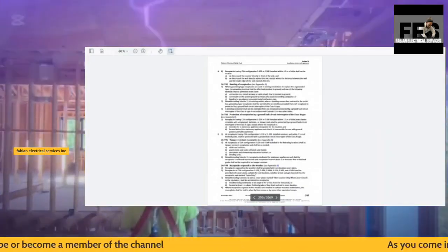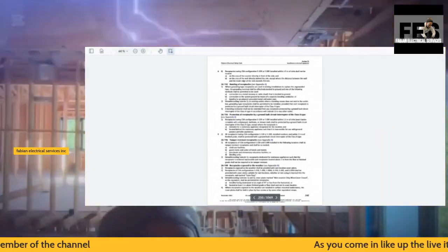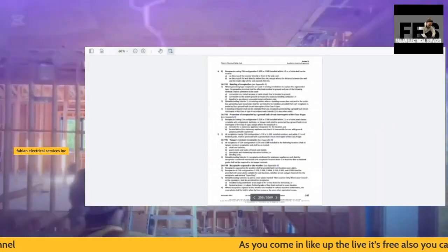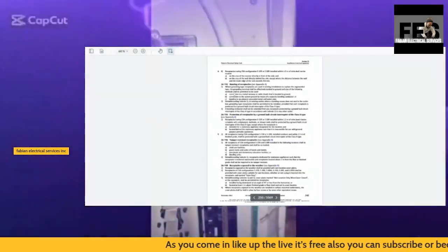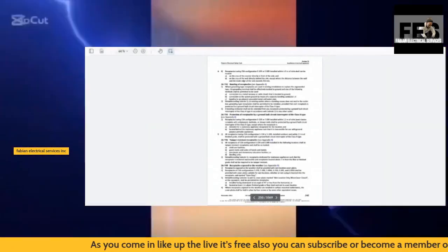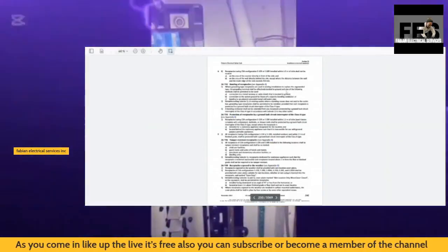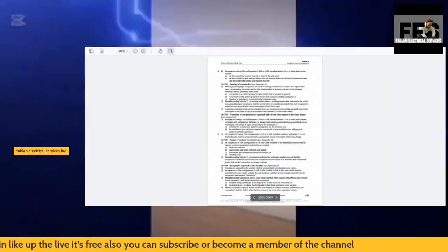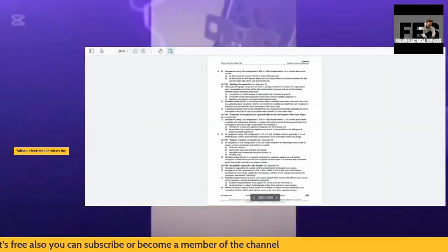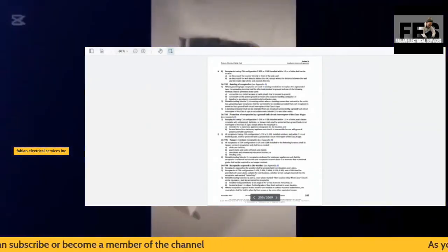So again, bonding of receptacles. Replacement grounding type receptacles are used in existing installations to replace the ungrounded type. The grounding terminal shall be effectively bonded to ground, and one of the following methods shall be permitted to be used. And again, I have used this in the past.